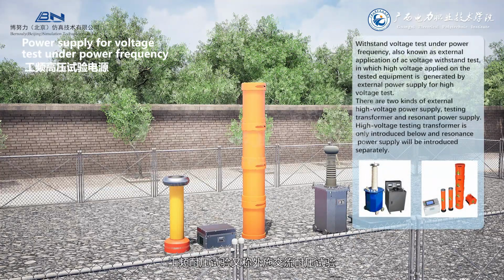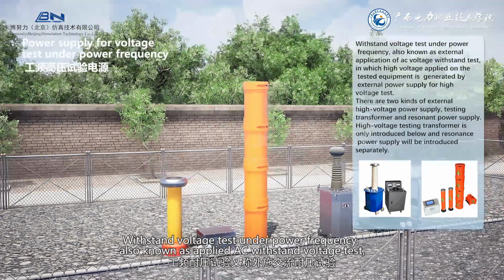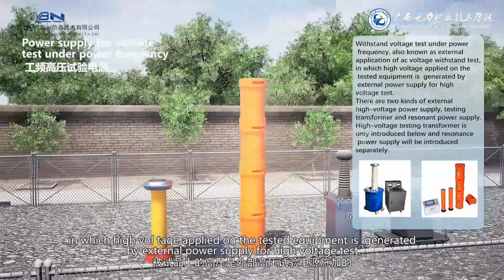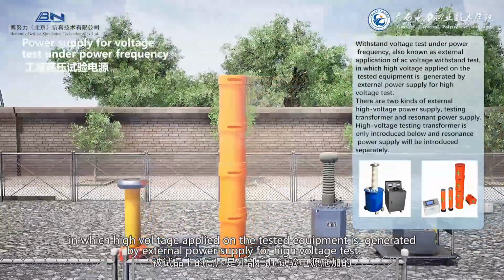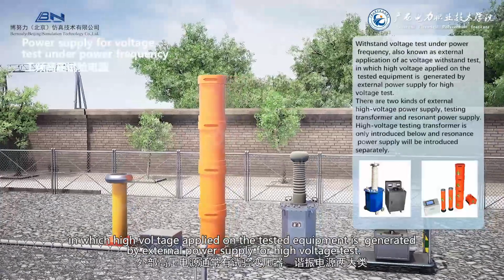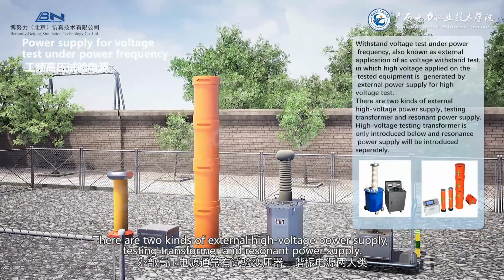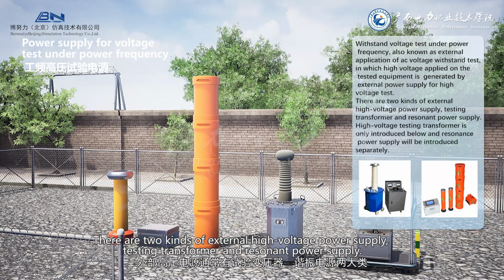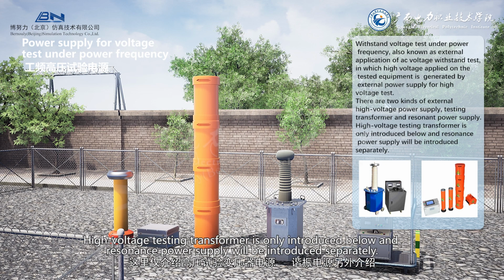Withstand voltage test under power frequency, also known as external application of AC voltage withstand test, is one in which the high voltage applied on the tested equipment is generated by an external power supply for high voltage tests. There are two kinds of external high voltage power supply: testing transformer and resonant power supply. Only the high voltage testing transformer is introduced below, and the resonant power supply will be introduced separately.